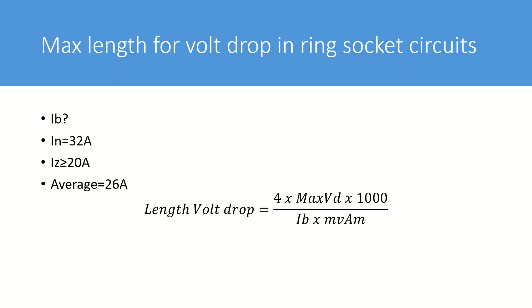So the equation can be carried out as follows. The max volt drop which will be 11.5 multiplied by four multiplied by a thousand and then divided by the design current which will be 26 amps multiplied by millivolts per ampere per meter.